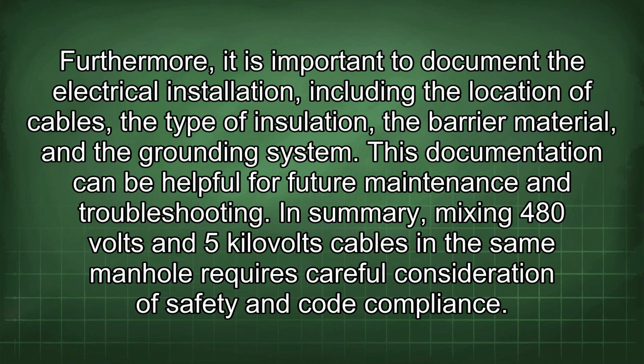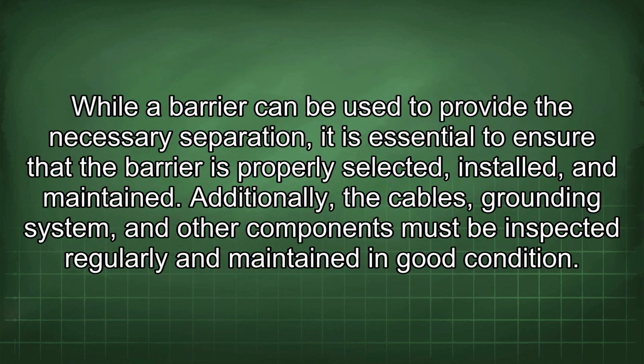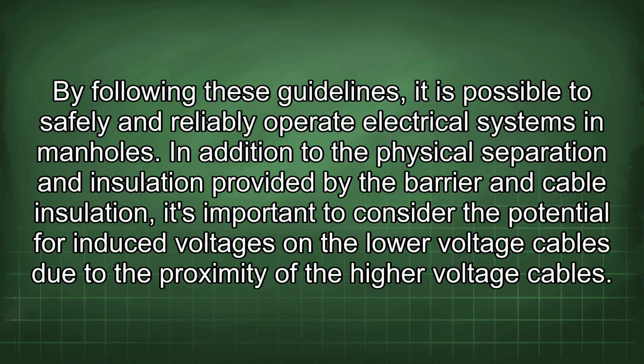In summary, mixing 480 volts and 5 kilovolts cables in the same manhole requires careful consideration of safety and code compliance. While a barrier can be used to provide the necessary separation, it is essential to ensure that the barrier is properly selected, installed, and maintained. Additionally, the cables, grounding system, and other components must be inspected regularly and maintained in good condition. By following these guidelines, it is possible to safely and reliably operate electrical systems in manholes.